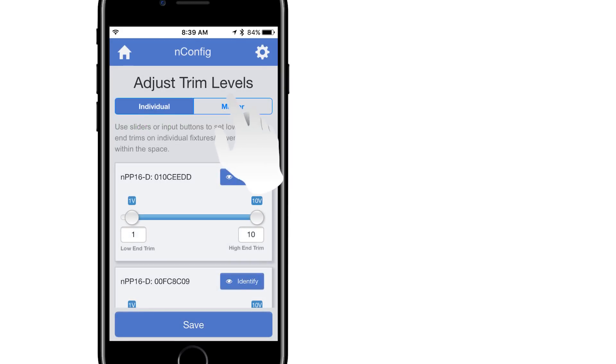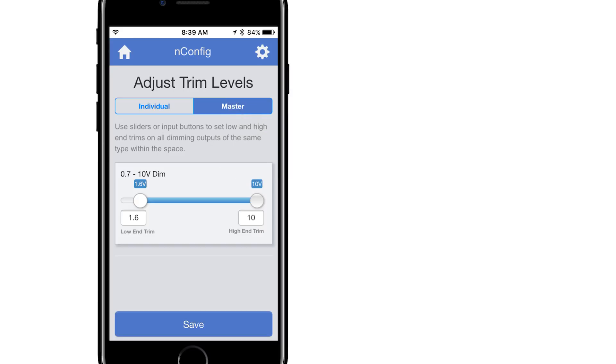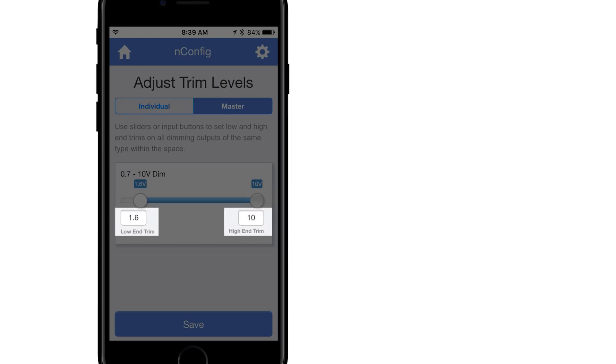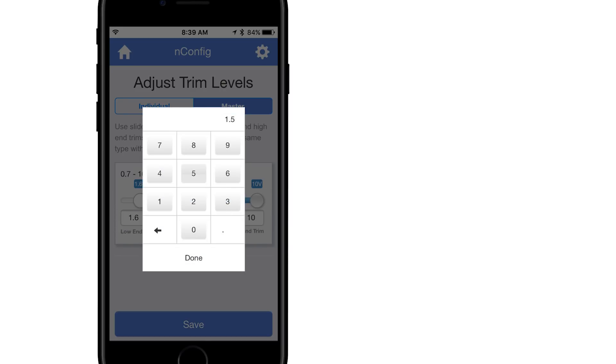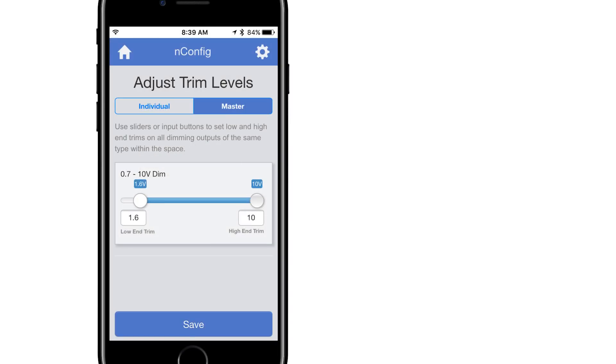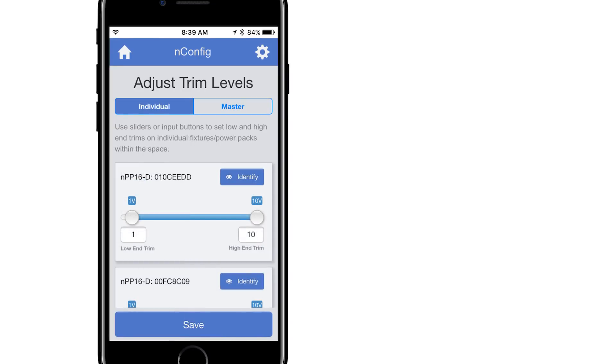Selecting Master is used to modify the trim levels of all the same dimming device types at once, such as 0-10 volt dimming or phase dimming devices. You can also use either the sliders or digital input boxes in Keypad to enter the desired values. Once complete, select Save to adjust the trim on all like devices.